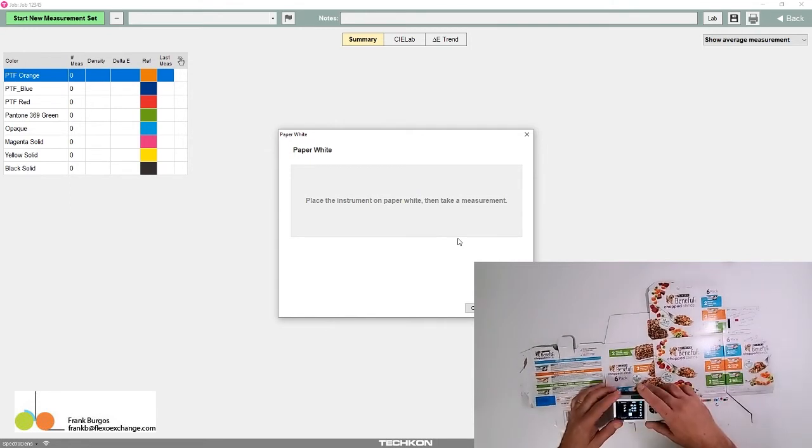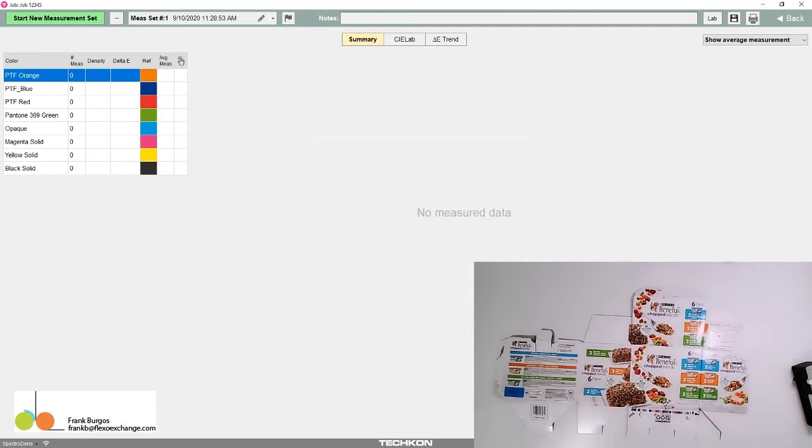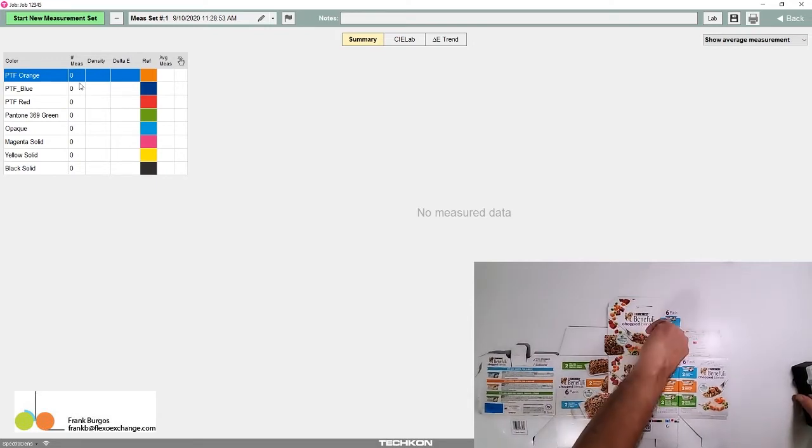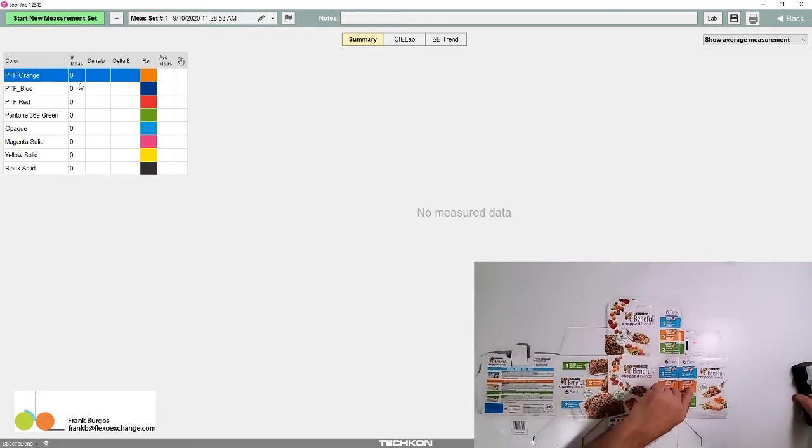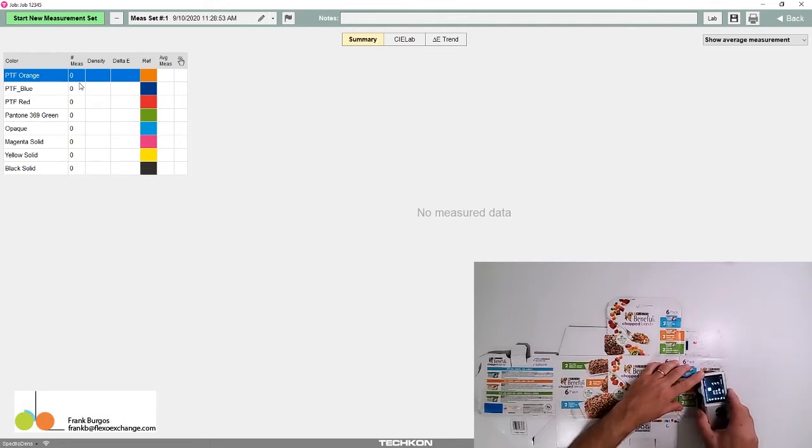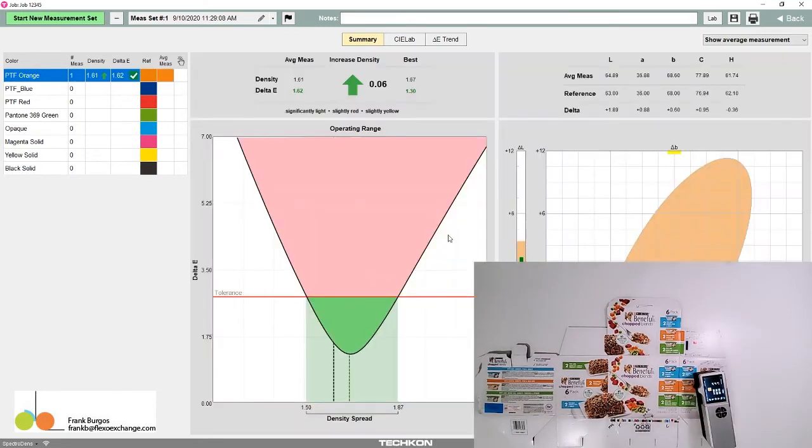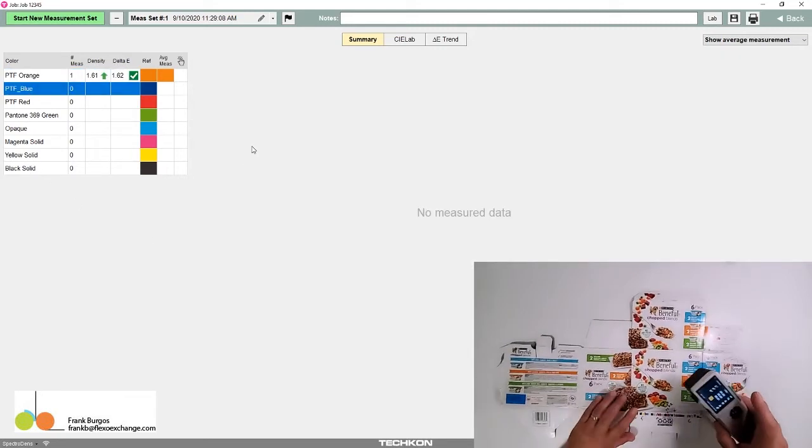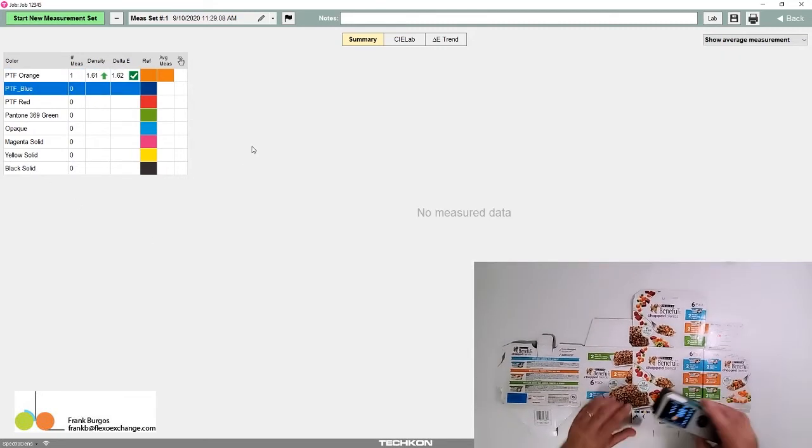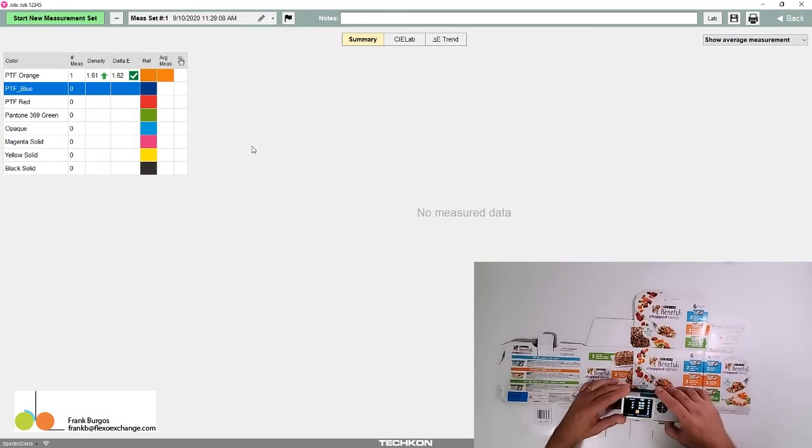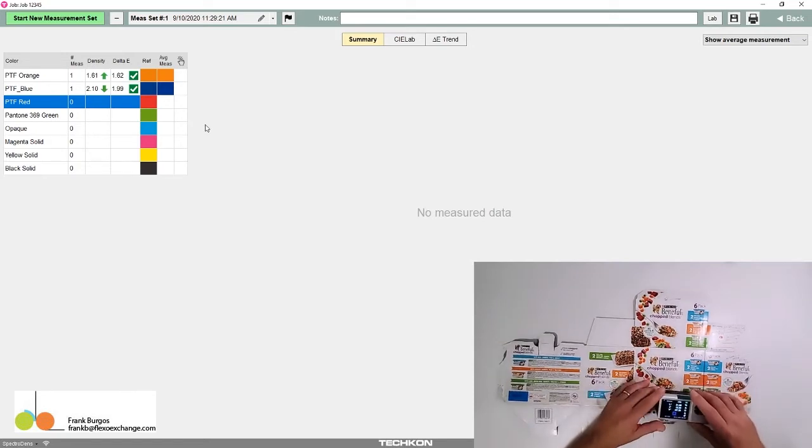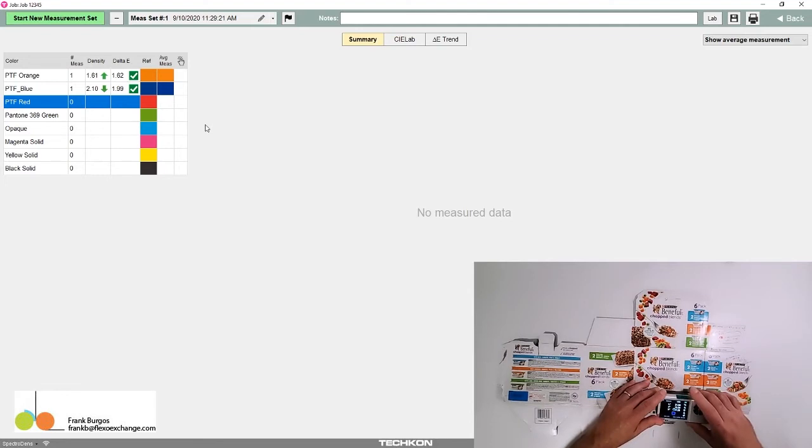Now I'm measuring PTF orange. Rather than measuring over here, let me measure this patch and see how it turns out. We passed, that's good. PTF blue is right here on this patch—looking good. PTF red right here. We have running patches so our operators can measure.